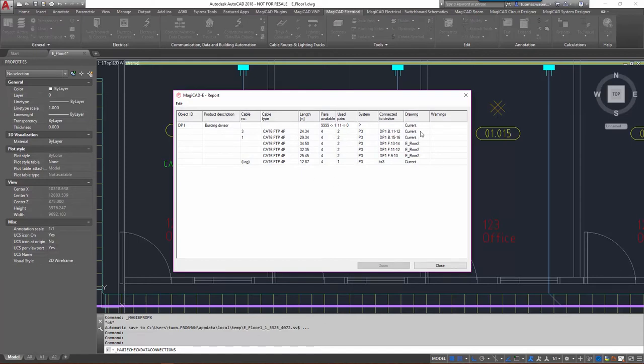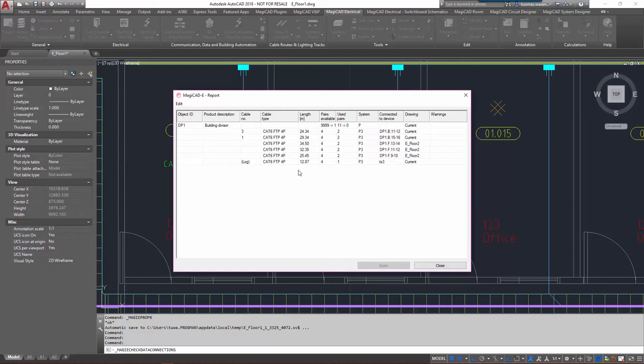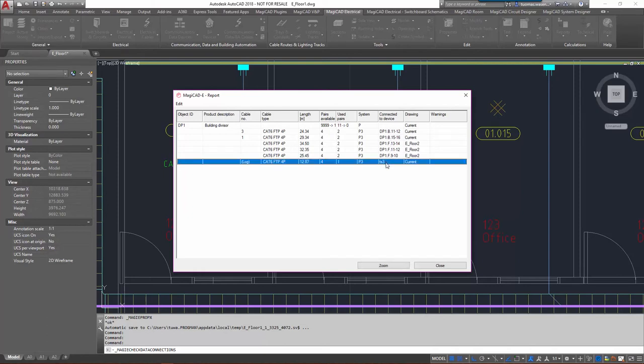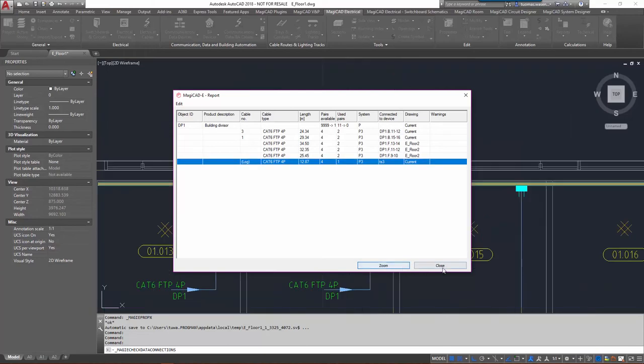And I can now see all the connected devices, three sockets from the current drawing and three from this eFloor2 drawing as well. And what we see here is the cable numbers, cable types, the lengths of course, systems, then the IDs for the actual device as well. Looks like one of the data sockets which is in the current drawing is without a cable number and also without an ID here, it's showing the user code instead of an ID.